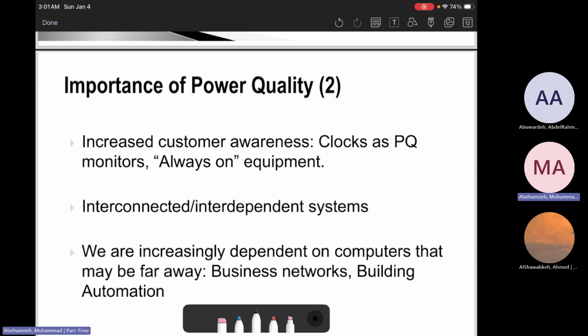The interconnected systems are the key. One small event can propagate into a bigger operational problem because everything is networked. A small sag can reboot a router, which disrupts cameras, which affects security, which triggers alarms. So sometimes this can make a false alarm, or sometimes it can disable the alarms. So power quality is not just a technical quality issue, it can be a service quality issue. For example, with security, if the cameras get damaged or are not working properly, this will make a big problem that we don't want.